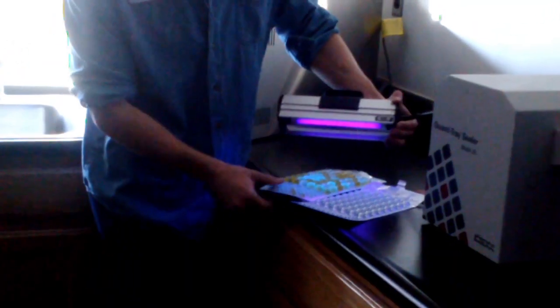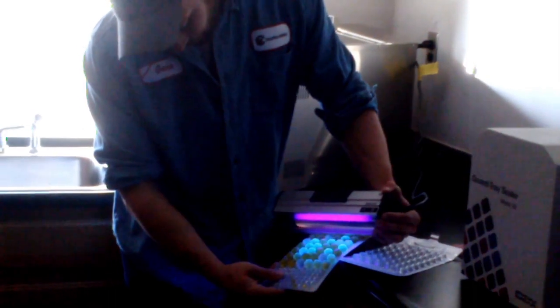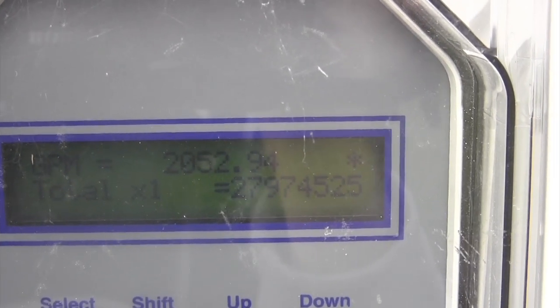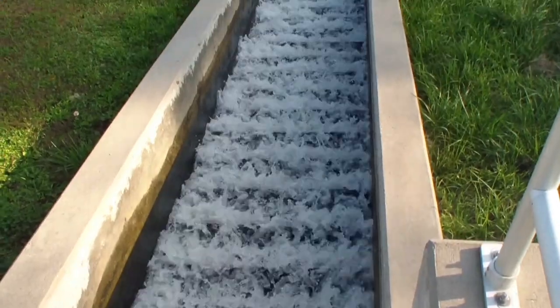At this point, the water leaves the clarifier and is tested for various chemicals and bacteria. In the lab, technicians use simple chemistry to check that no dangerous bacteria are present in large populations. At this point, the water is mostly free of contaminants. After testing, the water is then treated with high-power UV radiation, which kills almost all remaining bacteria. Finally, the water is reoxygenated as it flows through a set of stepped falls, then it is directed back safely towards the river.